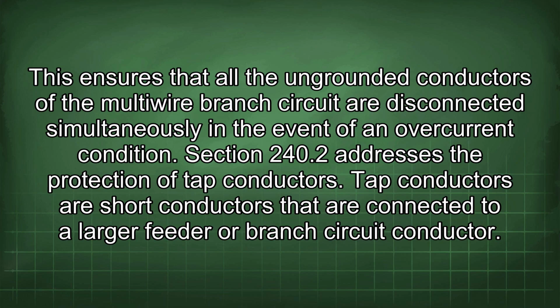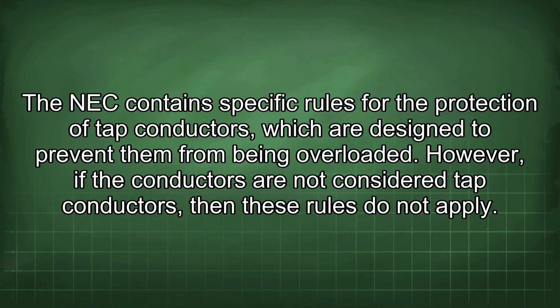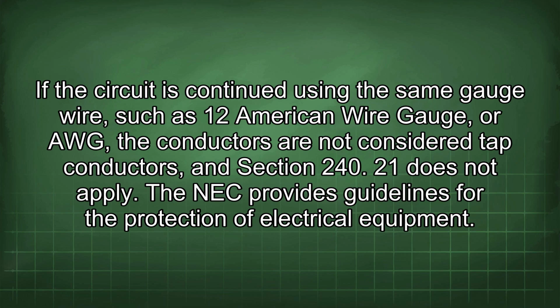Section 240.21 addresses the protection of tap conductors. Tap conductors are short conductors that are connected to a larger feeder or branch circuit conductor. The NEC contains specific rules for the protection of tap conductors, which are designed to prevent them from being overloaded. However, if the conductors are not considered tap conductors, then these rules do not apply. If the circuit is continued using the same gauge wire, such as 12 American wire gauge, or AWG, the conductors are not considered tap conductors, and Section 240.21 does not apply.